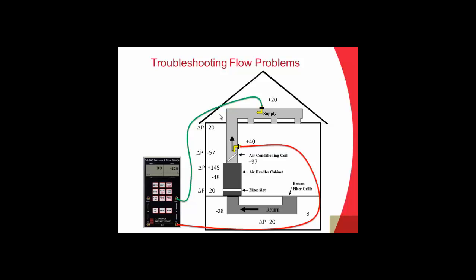intuitively, you would think that sealing the ducts, you'd be delivering more air to the room, and that's certainly true. You'll be delivering more of that air that you want delivered, but the total amount of air being delivered is going to be reduced. So maybe it won't change the airflow out of those registers as much as you think it will. All the air that's being delivered is going where it's supposed to go, but there'll be less total airflow going through the system. So sealing the ducts may not necessarily solve your comfort problem if you've got really high static pressures that are reducing the total airflow through the system.